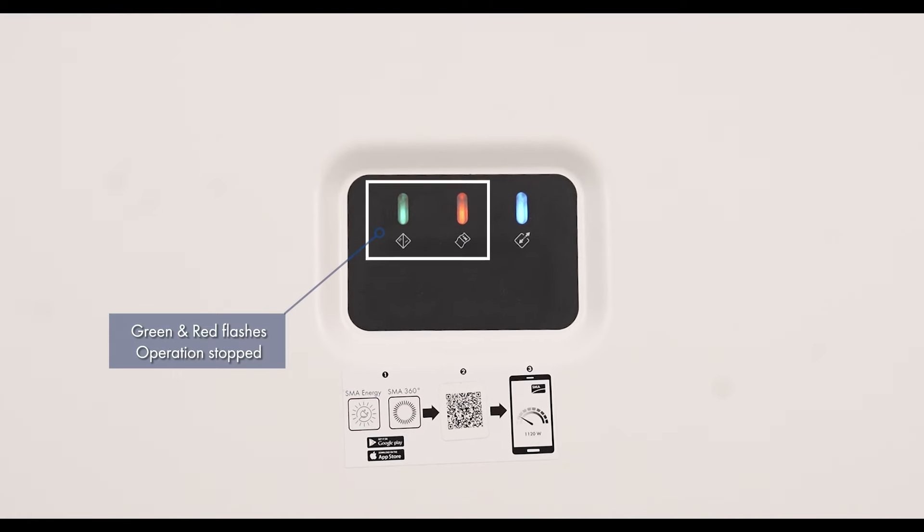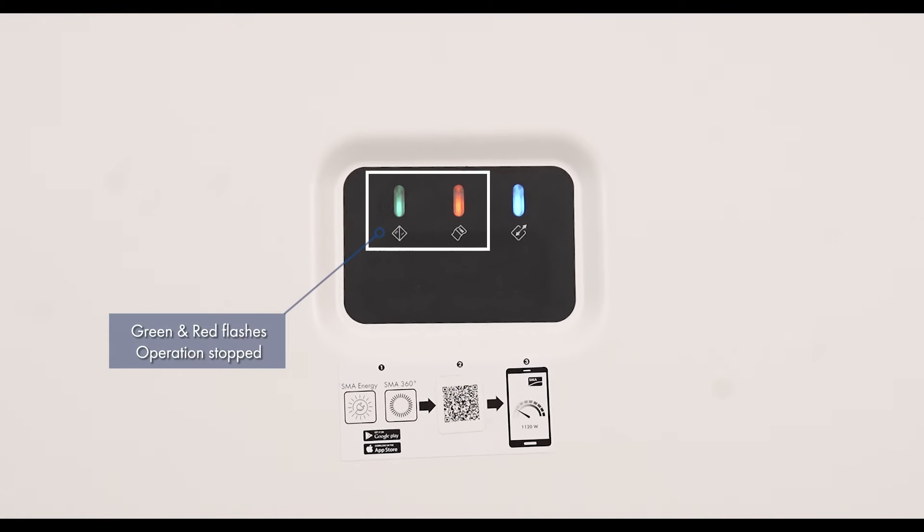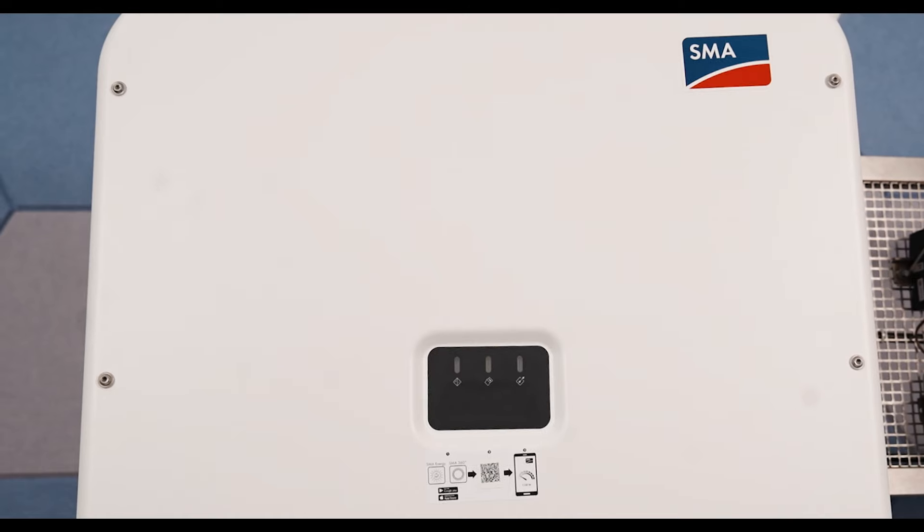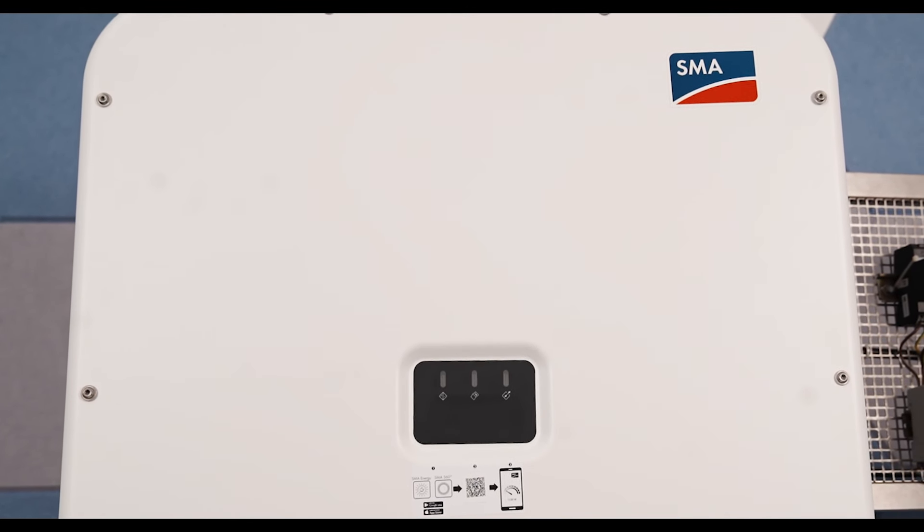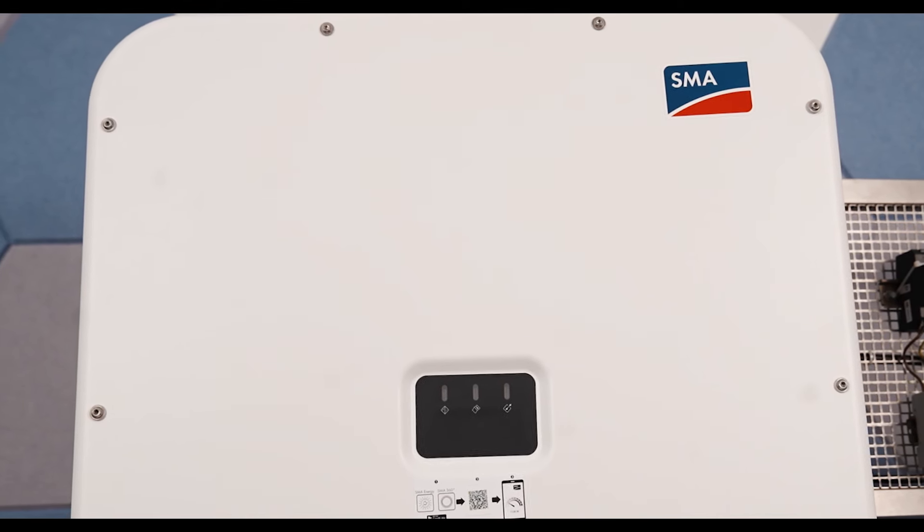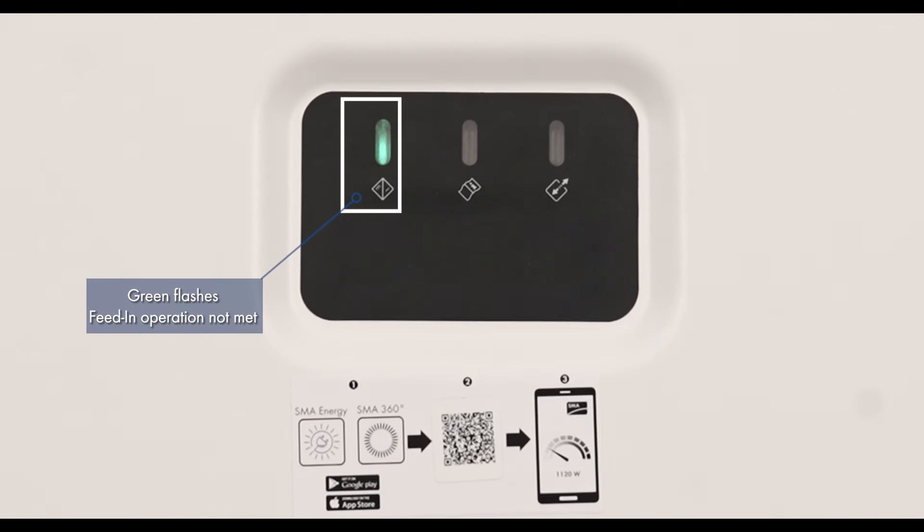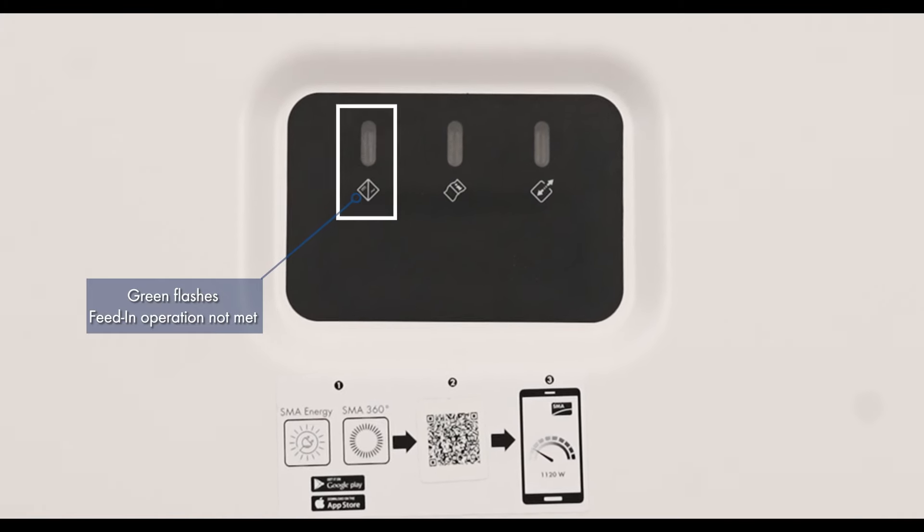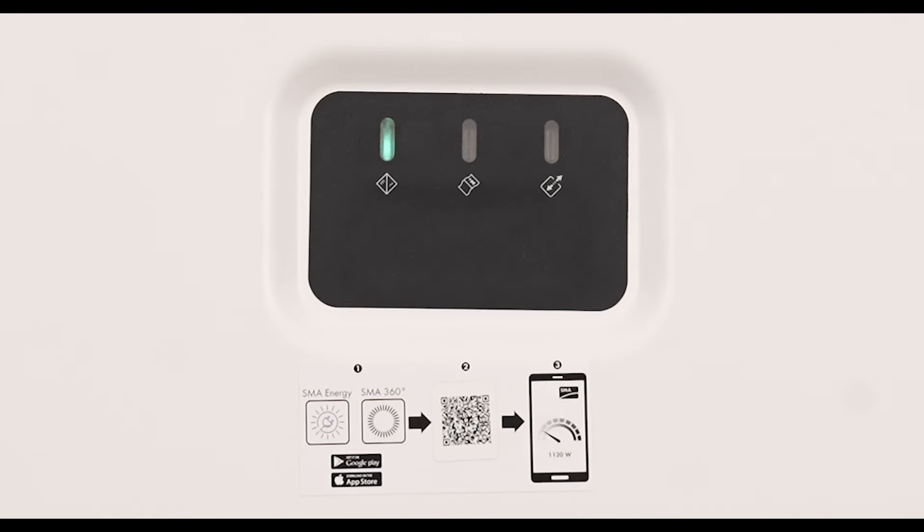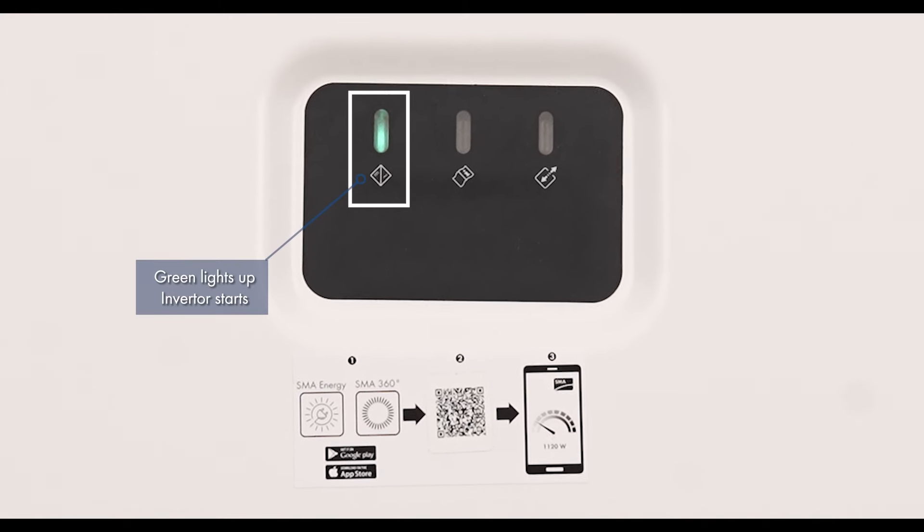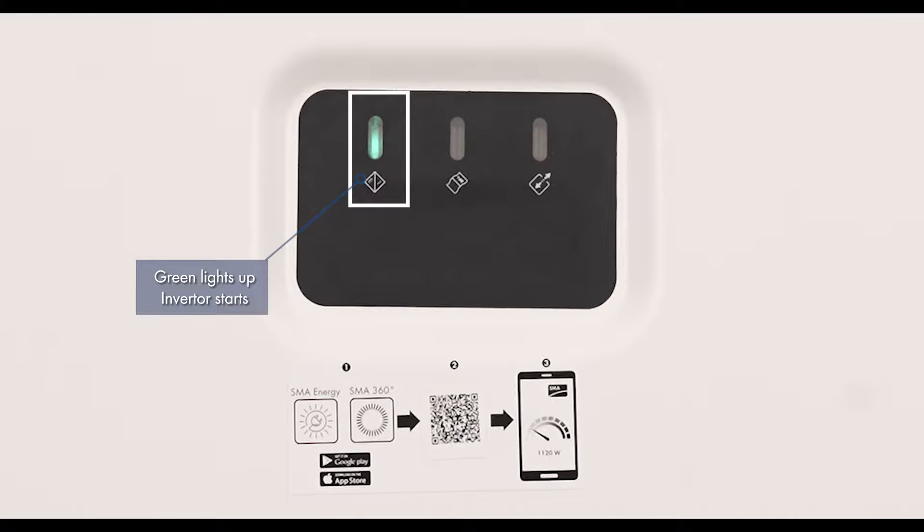If the green and red LEDs flash simultaneously during initial commission, operation is stopped because country data set selection is not done yet. For the inverter to begin operation, the configuration must be completed and a country data must be set. If the green LED is still flashing, the conditions for activating feed-in operation are not yet met. As soon as the conditions for feed-in operations are met, the inverter starts with feed-in operation, and depending on the available power, the green LED will light up continuously.